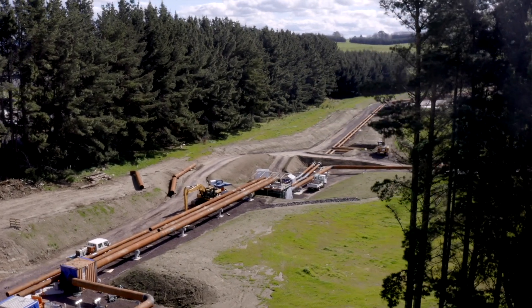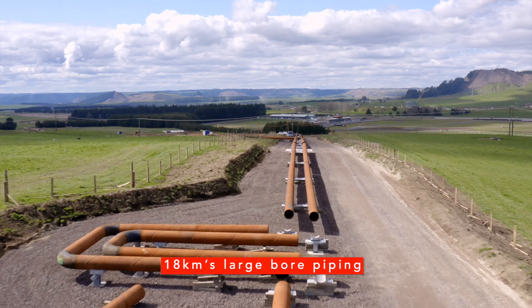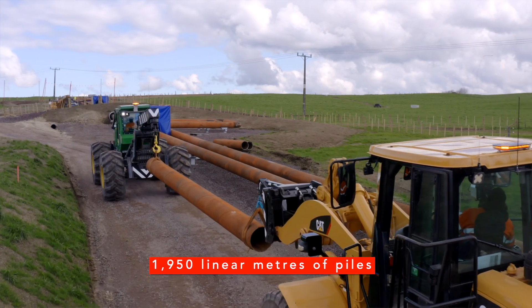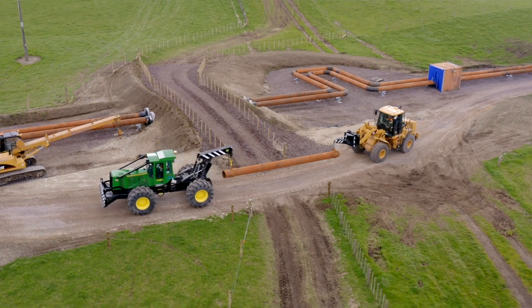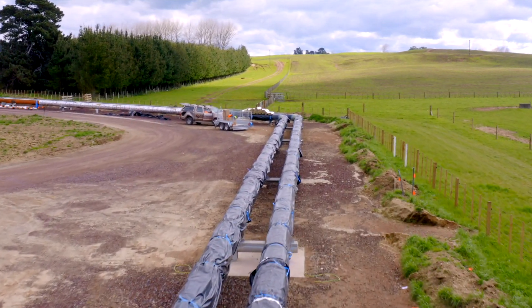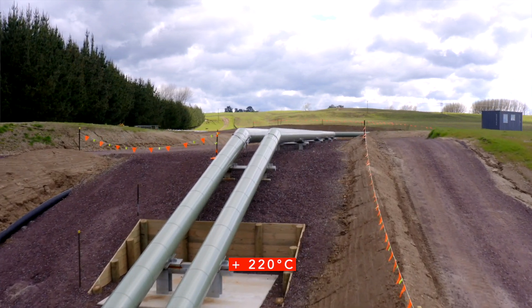The Tauhara steam field will have an extensive array of pipelines including over 18 kilometers of large bore piping. The hidden part of the pipeline includes around 400 tons of pipe support steel and 1,950 linear meters of piles that support the pipelines. Cross-country pipelines have an insulation and cladding system to protect people and animals from extremely high pipe temperatures, as the geothermal fluid traveling through the pipes comes out of the ground at temperatures in excess of 220 degrees centigrade.